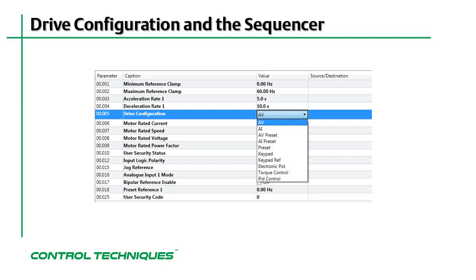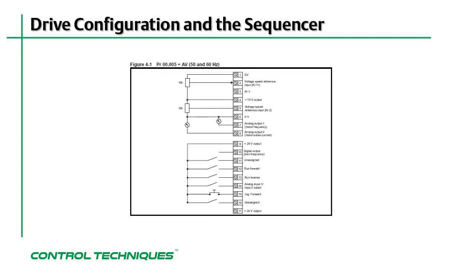The default setting for the US is AV. That means the drive is configured to receive its speed reference from an analog voltage source such as a potentiometer. The diagram is taken from the Unidrive M400 quick start guide that is shipped in the box along with every drive.